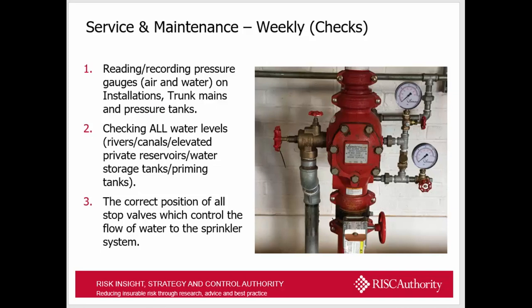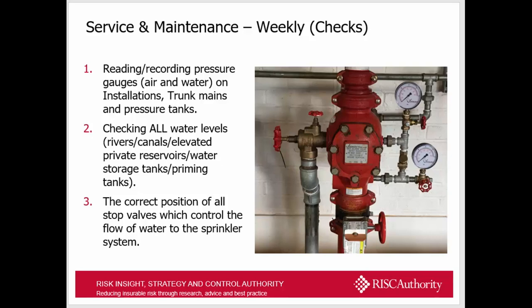I'll now run through the required service and maintenance activities to meet compliance with TB203. On a weekly basis, these are just checks: recording the pressure on the system; checking all water levels in storage tanks, rivers, canals, or private reservoirs; and checking the correct position of stop valves that control the flow of water to the sprinkler system. These are just visual checks to make sure things are in order.